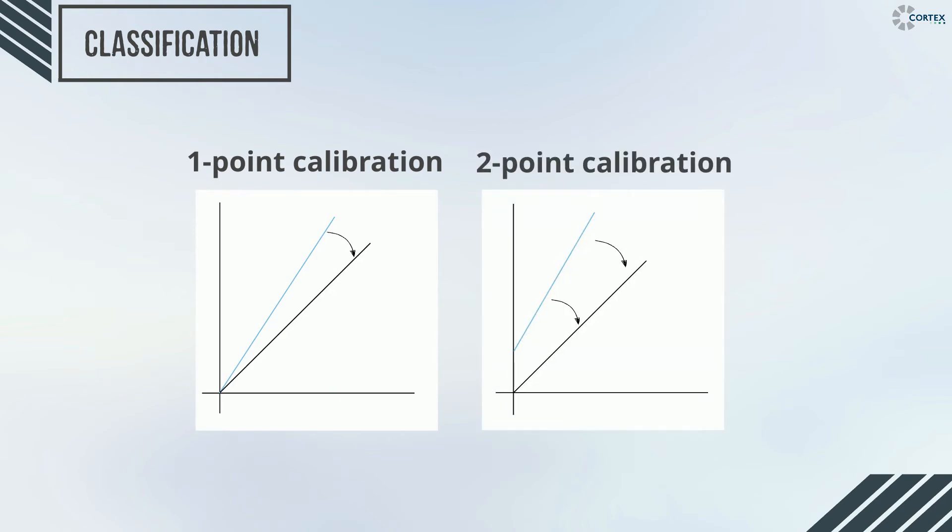Calibration in Cortex devices are classified into a one-point and two-point calibration. Both calibrations look at the linear relationship between a defined gas concentration and the measured gas signal that is collected from the sensor.